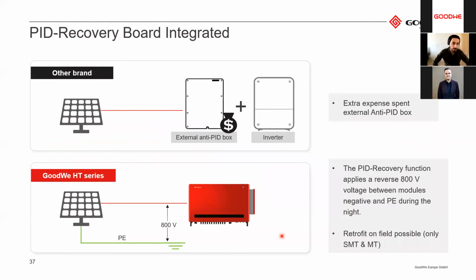Moreover, we have a PID recovery board integrated into the inverter. First I can explain what PID means. It is potential induced degradation of the PV modules, and it means that over time the modules will degrade. But to avoid this, you can install an anti-PID box, which will reduce this phenomenon and increase the yield overall. But then this additional box means additional installation cost, not only for the material, but also for the work done. In our inverters, it's integrated and can also be retrofitted in the field for our SMT and MT inverter. And what it does is that during nighttime, it applies a reverse voltage that repairs the damage that has been done during the daytime.